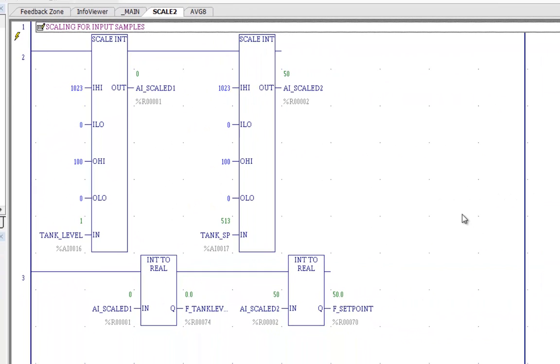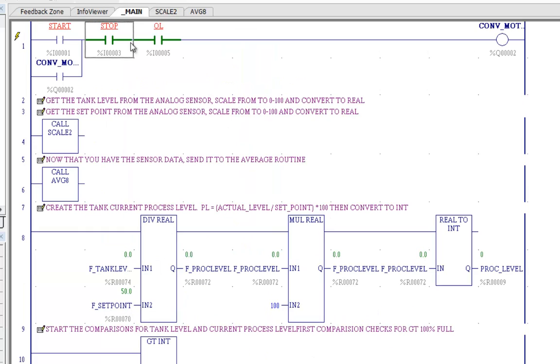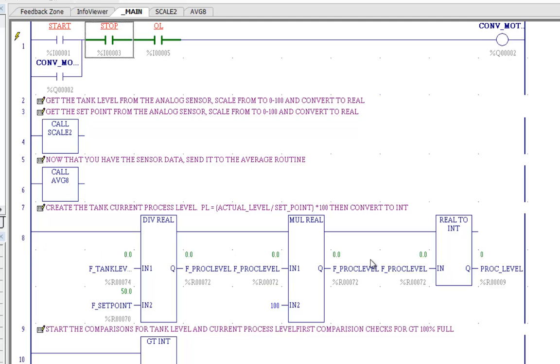This looks like another ladder program. It looks like any other program and what it will do is the PLC will transfer control to this program, start executing at the first rung, work its way through. When it's done with its rungs and there are no other additional rungs to process it will return right back where it picked up. So it will return to the next rung here which is rung 6 and then call average8. When average8 completes it will return back down here to rung 8 and then start processing from there.